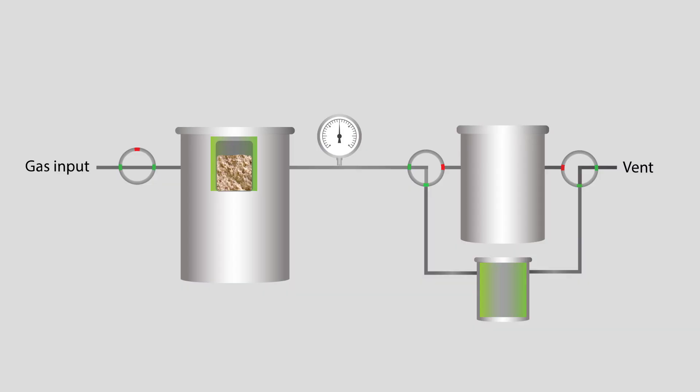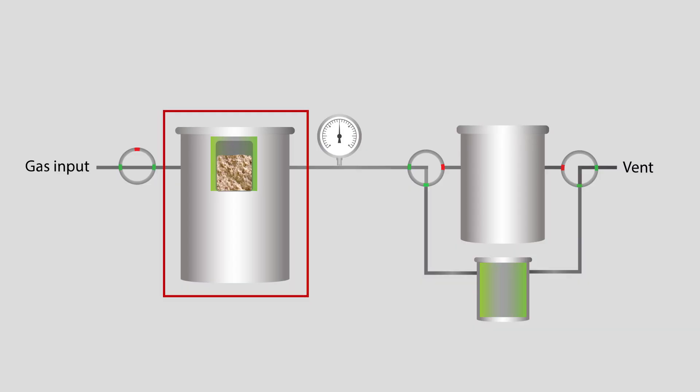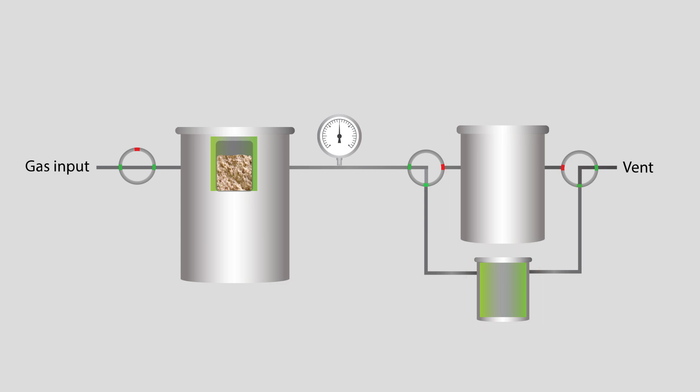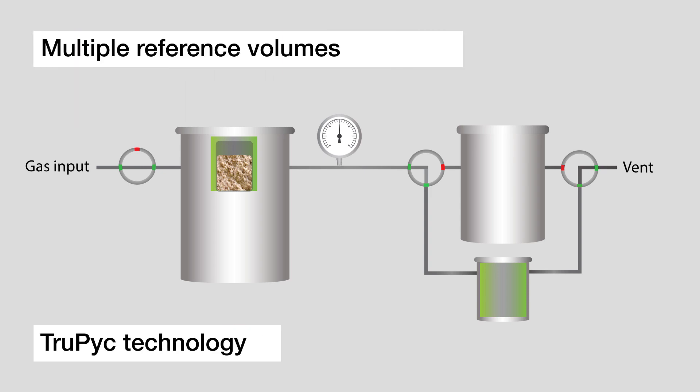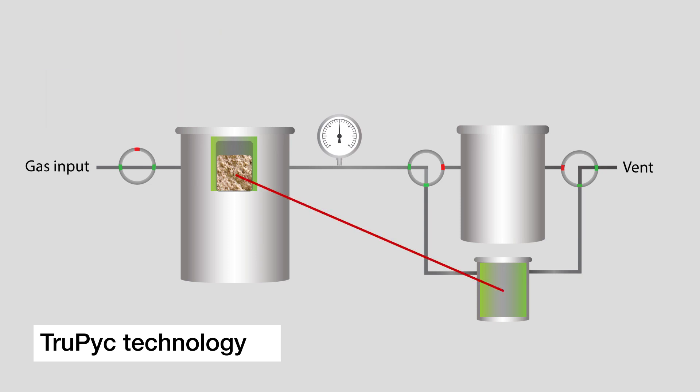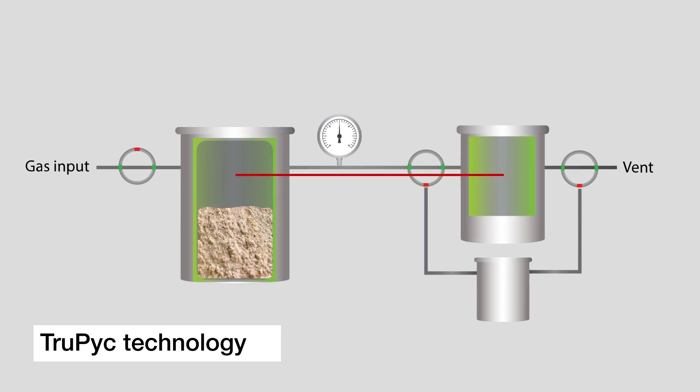Accurate pycnometric results rely on the ratio between the sample chamber volume and the volume of the reference chamber. Ultrapyc instruments feature TruPyc technology — the use of multiple built-in reference chambers — so you get the highest level of measurement accuracy whether your sample has only one cubic centimeter of solid volume or more than 100 cubic centimeters.